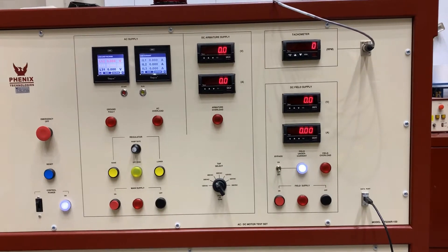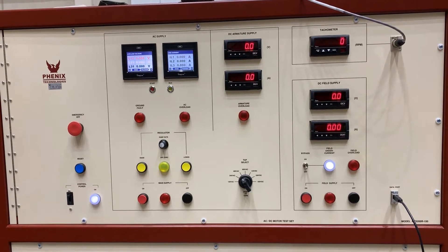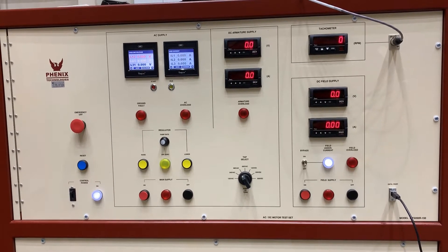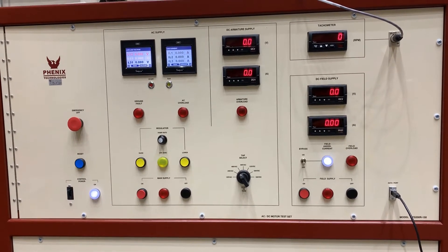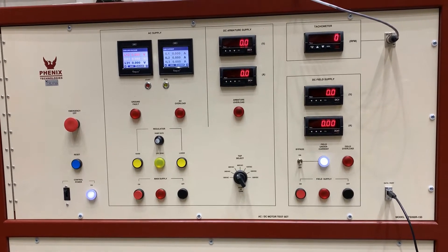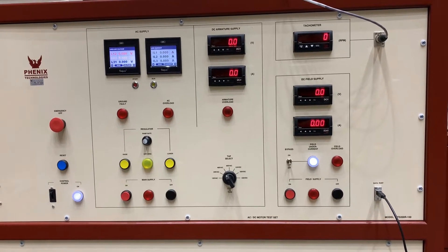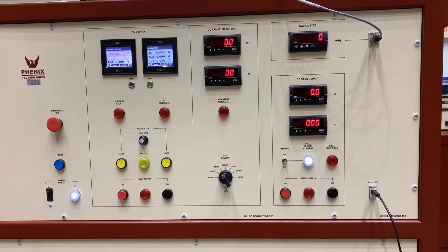Today we'll be going over the base controls of our Phenix test set MTS 200R-150. This is one of our D model series, which range from 200kVA up to 1000kVA. We also have our standard R models which go clear up to 7500kVA and include many extra features that this unit does not.